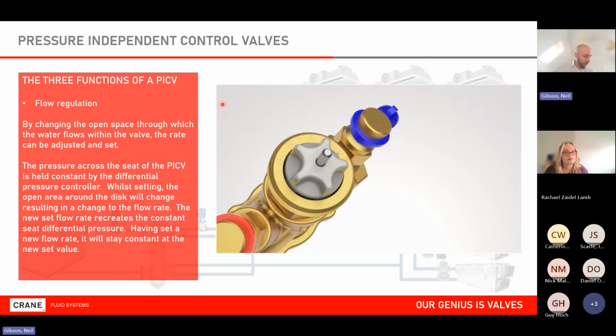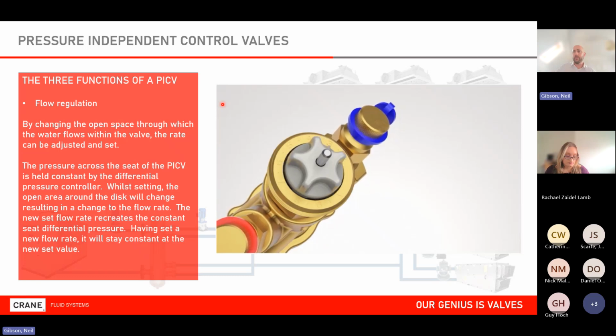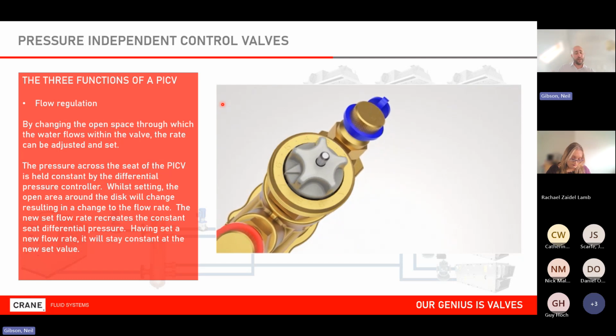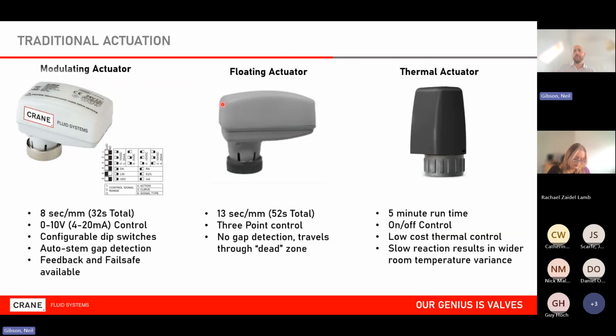One of the issues I highlighted before with 2-port valves is that you needed to go around and balance everything off in a systematic process. With a PICV, I can set the flow rate on the dial, and I can do it independent to any other coil on the system. So again, I'm speeding things up here. I'm simplifying the system. I still have to set that dial. I still have to climb a set of ladders, try to find that dial, and then turn it to a number which is, for the best will, quite hard to see in a dark ceiling void. So I still have to do that manual process. I've improved things, but still not perfect. And I still have to put an actuator on there.